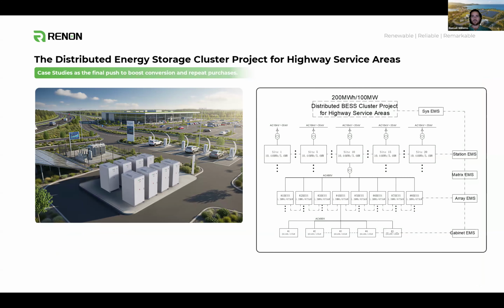There tends to be more ways to generate revenue or reduce costs than you'd expect at first glance. The way a system like this might operate, you can actually get to pretty high scale: you run these batteries at the array level, with a set of five per array. Each array of five can then be blended into what creates a matrix, allowing you, even in a very remote place, to have megawatts of storage, since there's no real maximum parallel limit as long as you're operating at the five-cabinet-per-array structure, with arrays combined into a matrix. This is exactly what our EMS is intended to do, building and scaling up to this level of operation, which is really impressive.